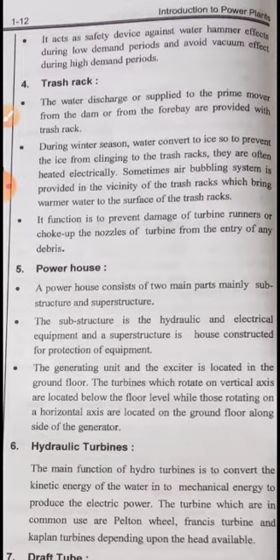Trash rack. The water discharged or supplied to the prime mover from the dam or from the forebay is provided with a trash rack. During winter, water converts into ice, so to prevent ice from clinging to the trash rack, they are often heated electrically. Sometimes an air bubbling system is provided in the vicinity of the trash rack, which brings warmer water to the surface of the trash rack. Its function is to prevent damage to the turbine runner or choking up of the nozzle of the turbine from the entry of any debris.